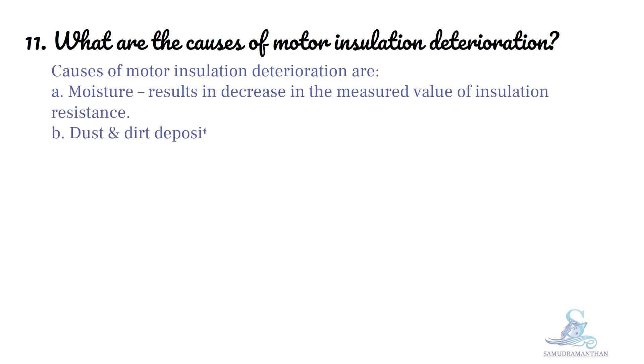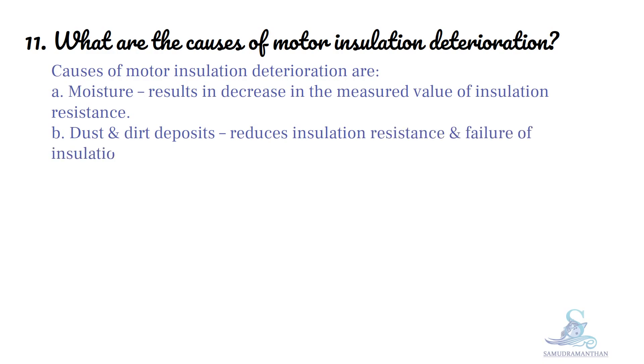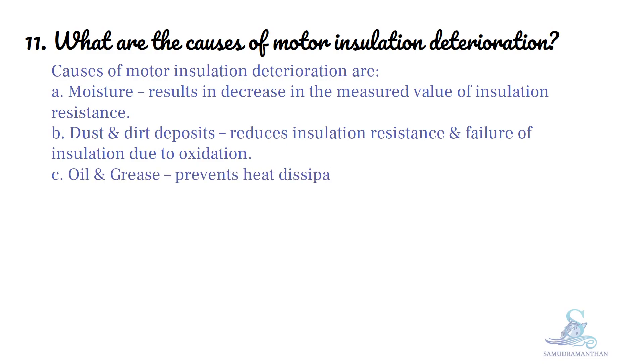Dust and dirt deposits reduce insulation resistance and cause failure of insulation due to oxidation. Oil and grease prevent heat dissipation and cause dirt and dust to settle on the insulation.